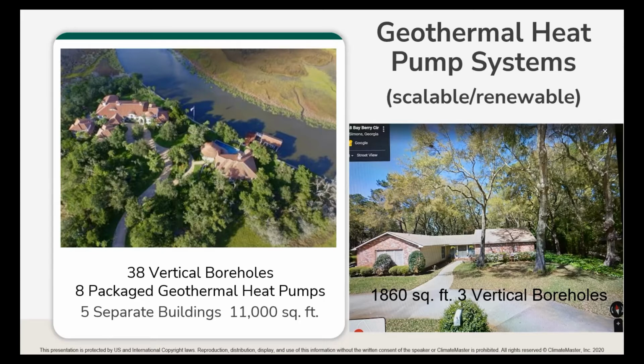The photograph on the right, or the home on the right, is 1,800 square feet or thereabouts. 3 vertical boreholes will allow the homeowner to reject the amount of heat that structure takes in on an hourly basis into water, and have those BTUs, that heat, be rejected into the ground and maintain the required indoor temperature at the thermostat, whatever that may be.